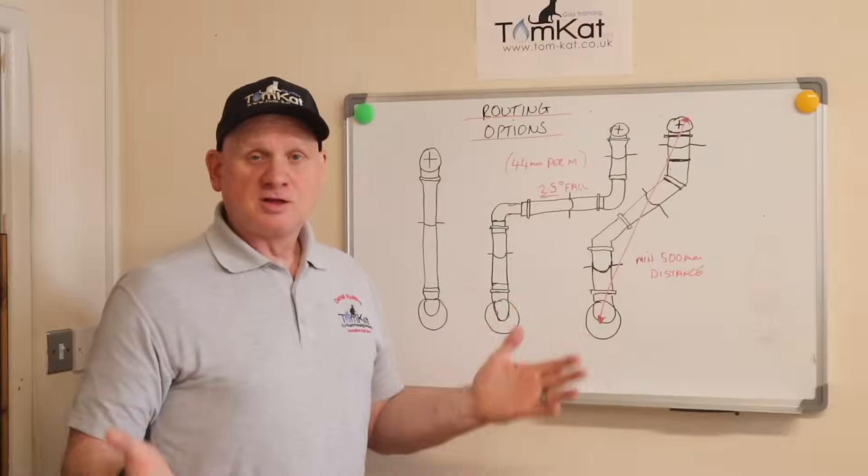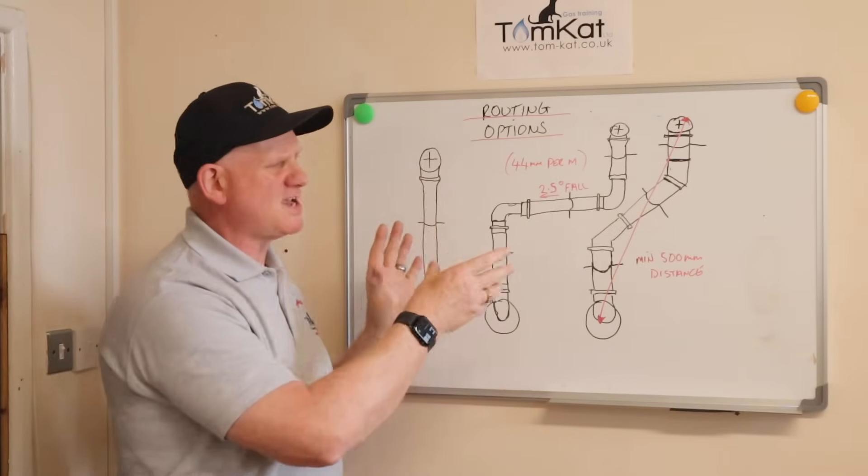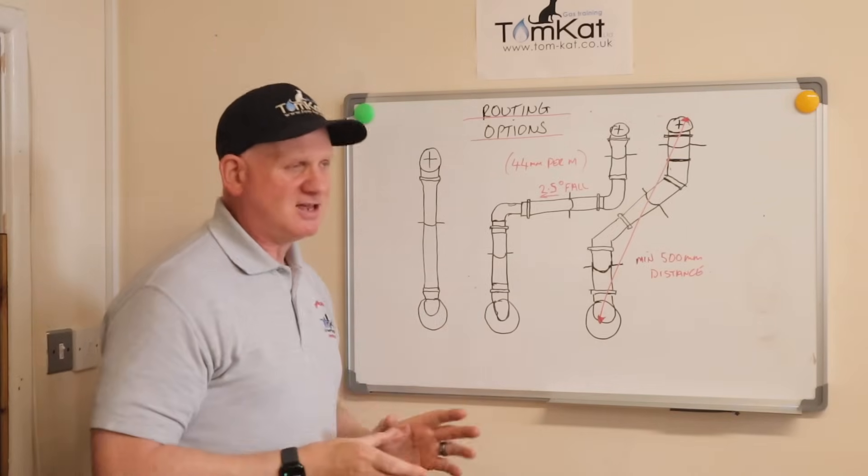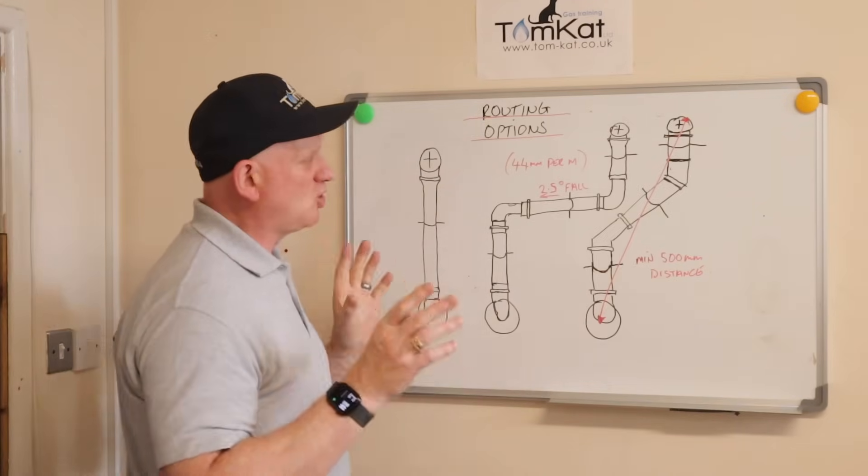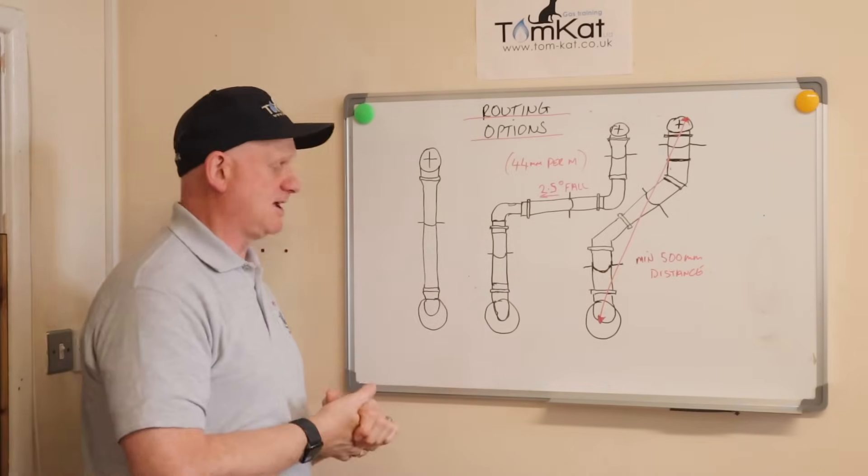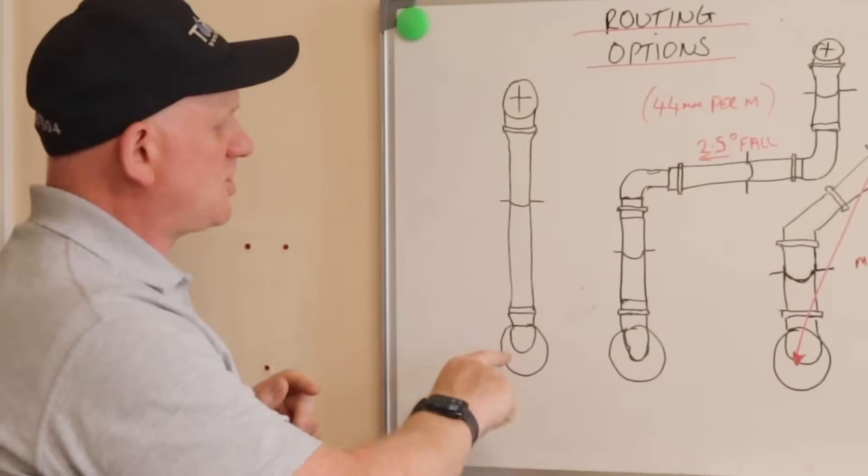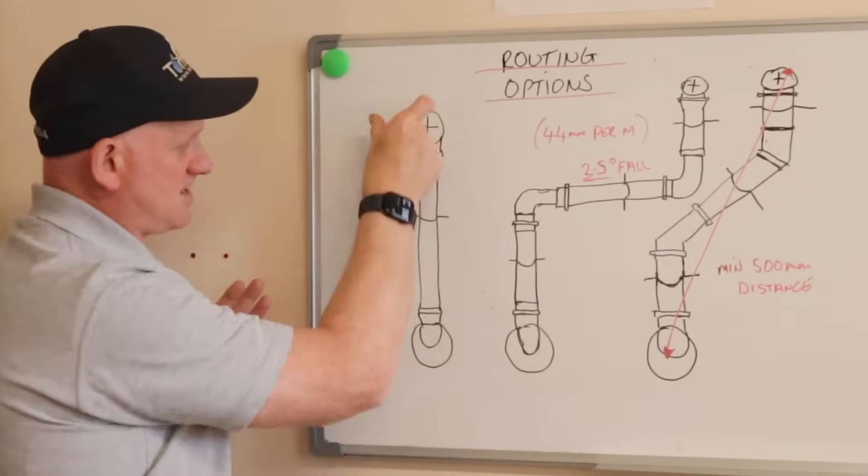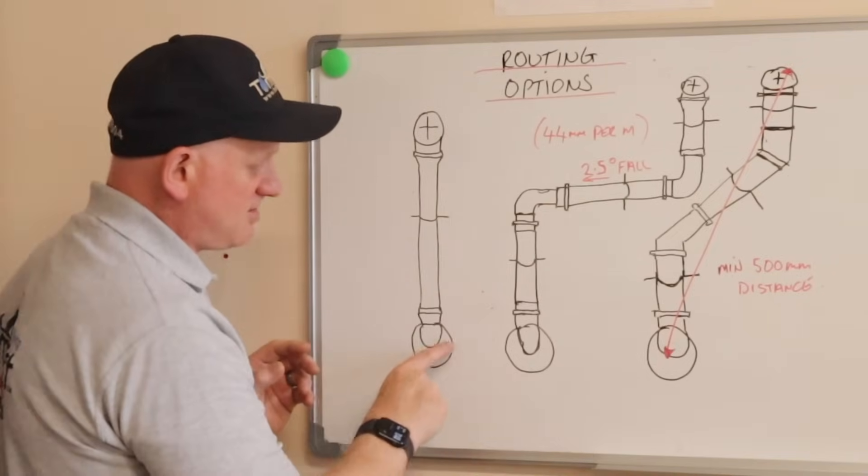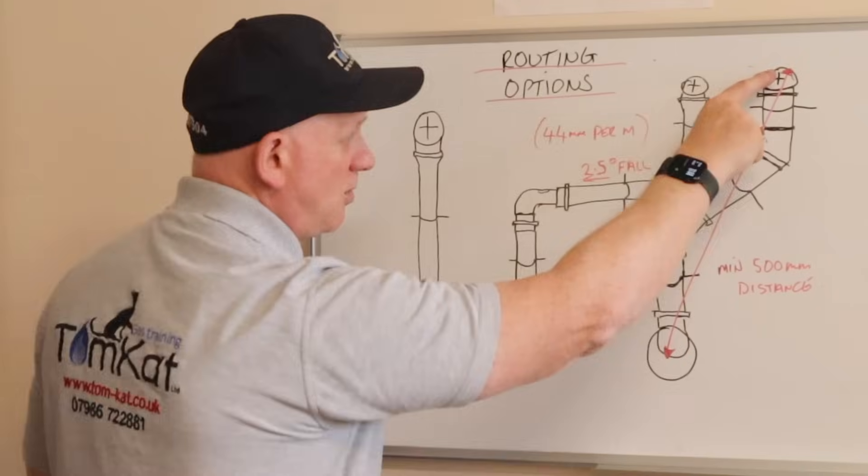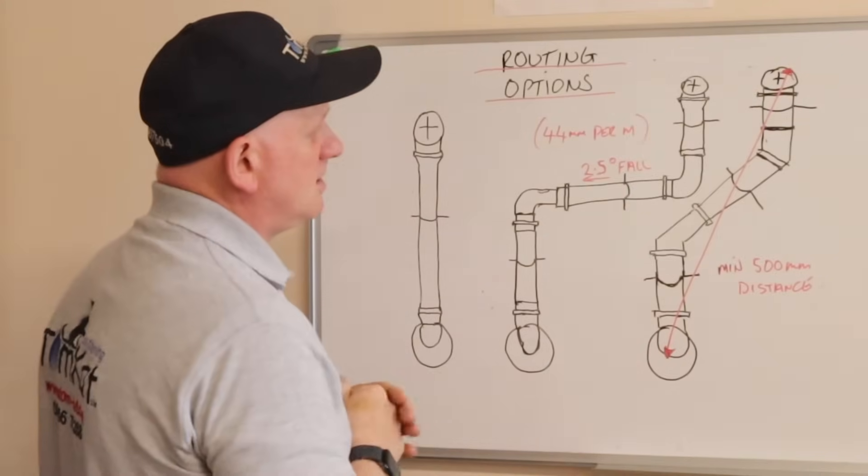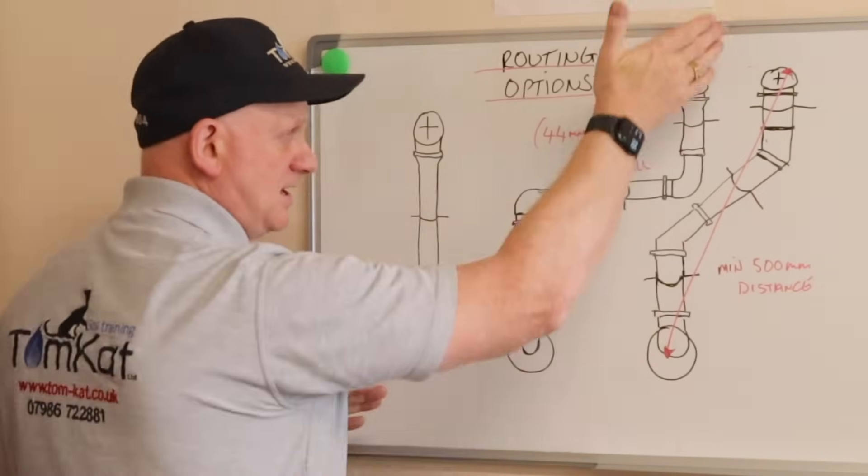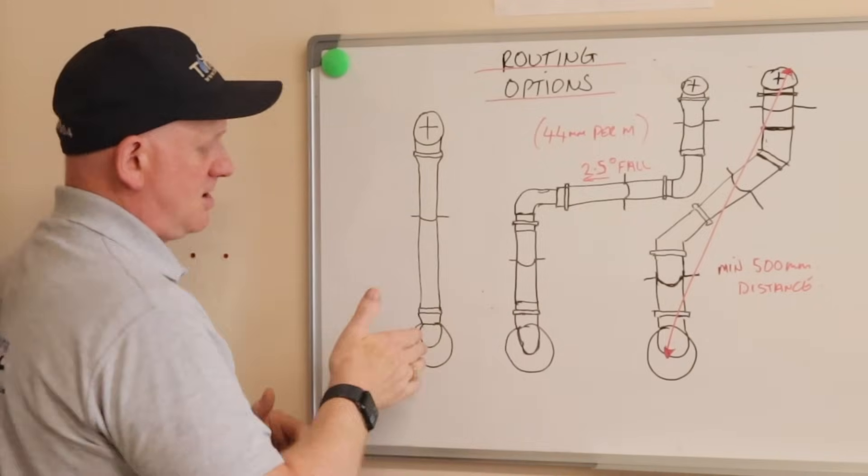So let's have a look at the routing options. Now this is pretty much standard with most of the boiler manufacturers, but again, check the manufacturer's instructions before you install a plume management kit. Now, most of them want you to go up before you go across, if that makes sense. So this is the standard plume management kit. Remember, from the centre of your terminal to the top of the bend at the top of the plume management kit it has to be more than 500mm in a diagonal.